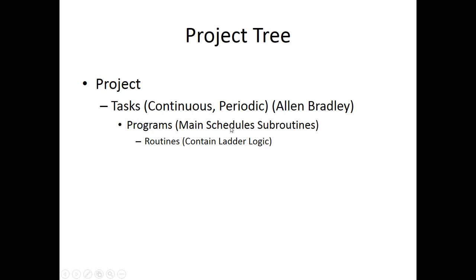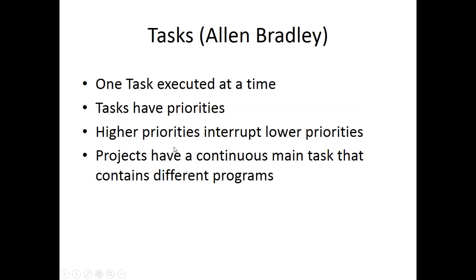And we talked about what was continuous and what was periodic. We also talked about how the routines are what gets scheduled or called out of the programs, and these contain the ladder logic or the FBD. These contain the logic, but they don't run unless they're called. Okay, so one task can be executed at a time. This is on Allen Bradley.